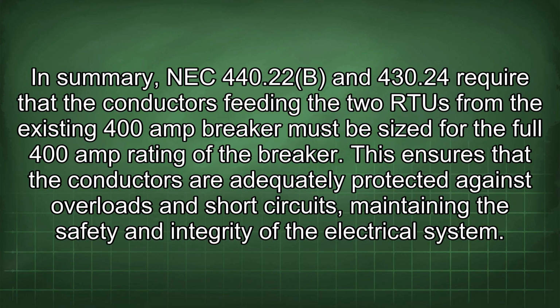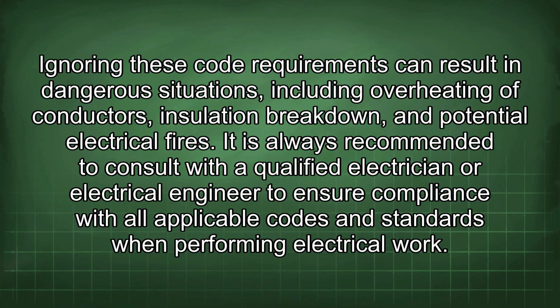In summary, NEC 440.22(B) and 430.24 require that the conductors feeding the two RTUs from the existing 400 amp breaker must be sized for the full 400 amp rating of the breaker. This ensures that the conductors are adequately protected against overloads and short circuits, maintaining the safety and integrity of the electrical system. Ignoring these code requirements can result in dangerous situations, including overheating of conductors, insulation breakdown, and potential electrical fires. It is always recommended to consult with a qualified electrician or electrical engineer to ensure compliance with all applicable codes and standards when performing electrical work.